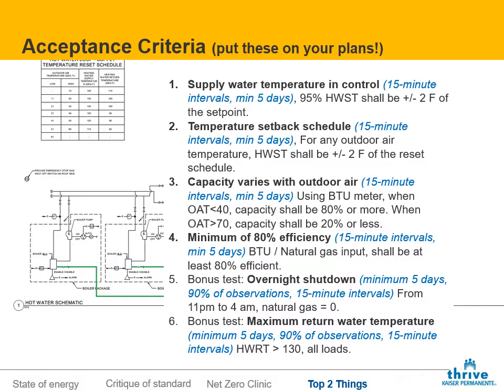And there should never be an hour where the natural gas input is 20 or 25% higher than the system demand that we see in that hour. That would be an 80% efficient boiler, right? And then there's 2 bonus tests here.